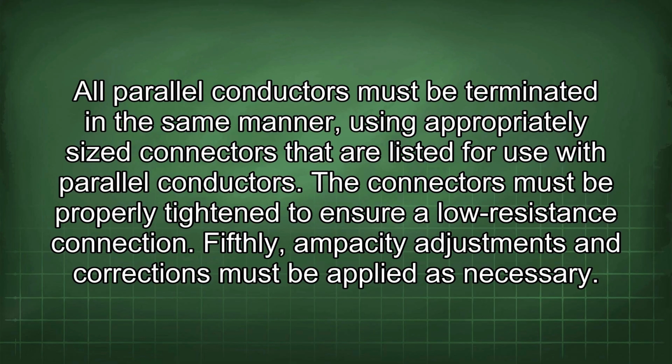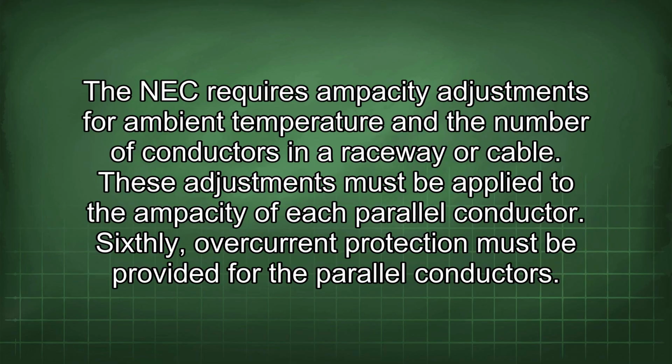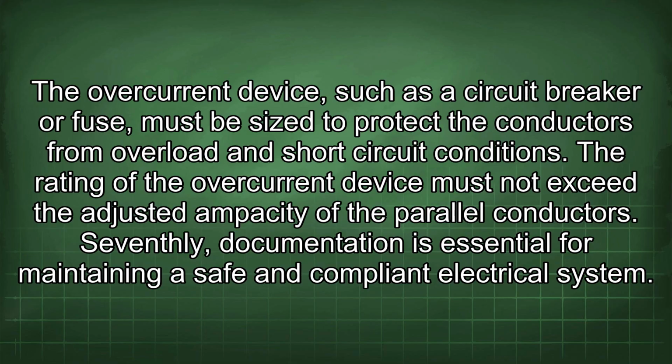Fifthly, ampacity adjustments and corrections must be applied as necessary. The NEC requires ampacity adjustments for ambient temperature and the number of conductors in a raceway or cable. These adjustments must be applied to the ampacity of each parallel conductor. Sixthly, overcurrent protection must be provided for the parallel conductors. The overcurrent device, such as a circuit breaker or fuse, must be sized to protect the conductors from overload and short-circuit conditions.